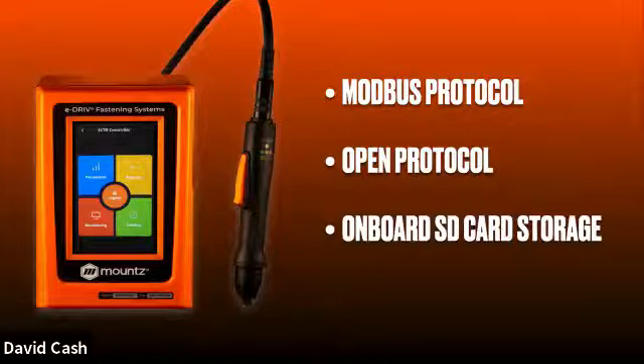But if you don't have an MES system or an internal network for the controller, and you still want the ability to capture what's happening with your assemblies and have that torque data, we can do that with an SD card stored on the controller. After every operation or event change, information is sent to that SD card, and periodically the card can be removed, the information downloaded, and the card reinserted into the controller.